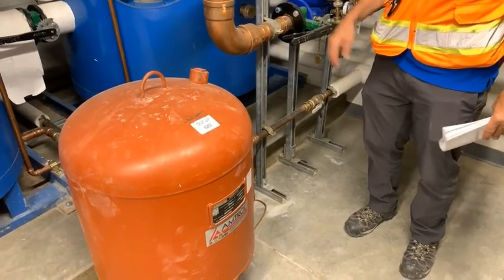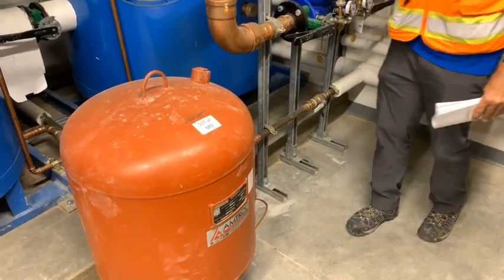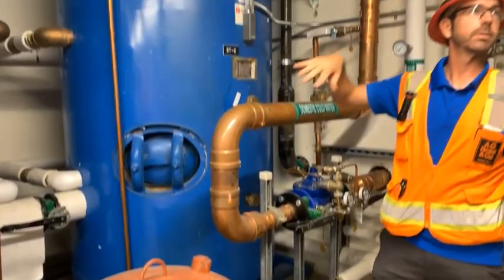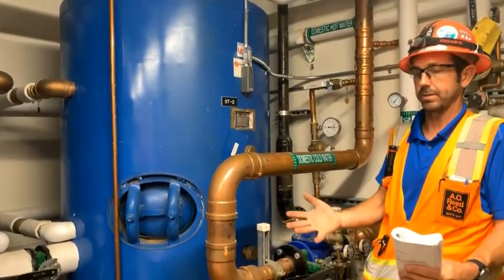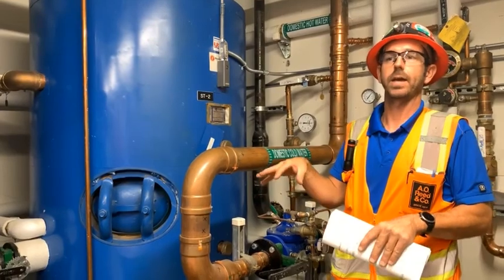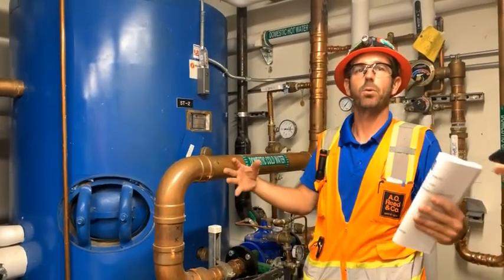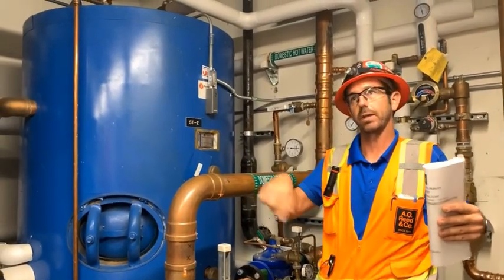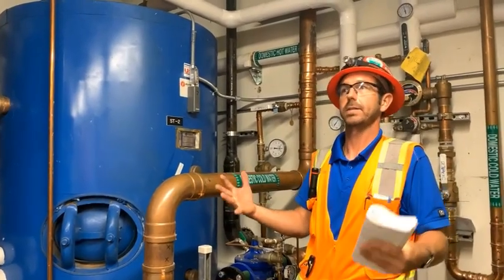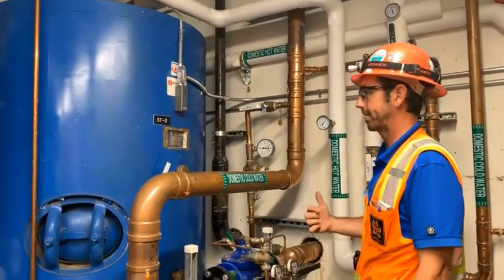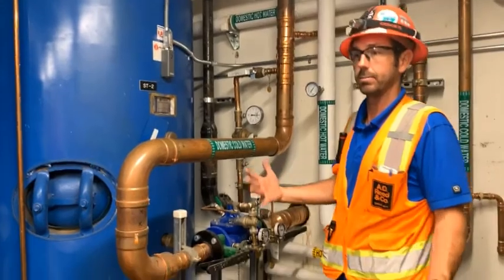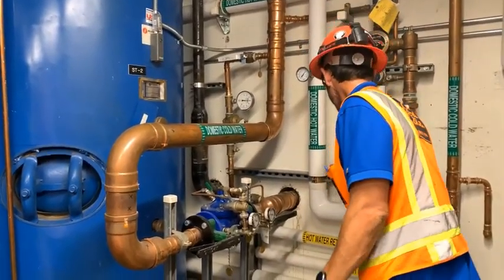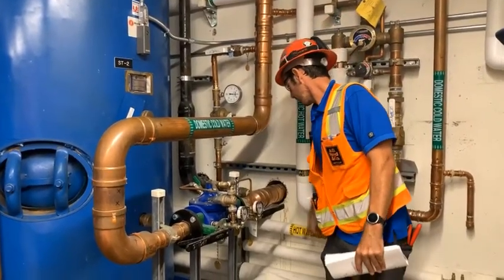What's the charge in it? The charge is 78 pounds. Our set point's 80, our high set point's 80, so we want a couple pounds under that. Okay, that way if the system heats up. So the domestic has an expansion tank because at some points it becomes a closed loop with a circulating pump. So if there's any expansion in that system, it will go into this tank instead of into the piping system, which could possibly burst the piping. And that's coming off the hot water line, okay?